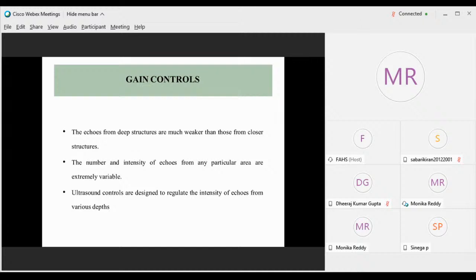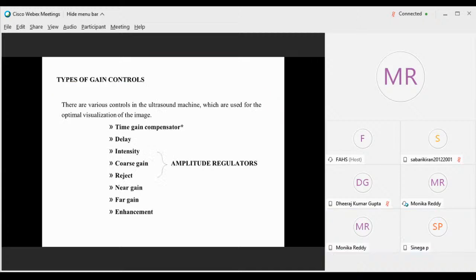There are several types of gain controls. The time gain compensator is a major, basic, and very important one. There are also delay control, intensity control, coarse gain control, reject control, near gain, far gain, and enhancement controls. Intensity control, coarse gain control, and reject control are together known as amplitude regulators. They regulate the amplitude of the echoes.